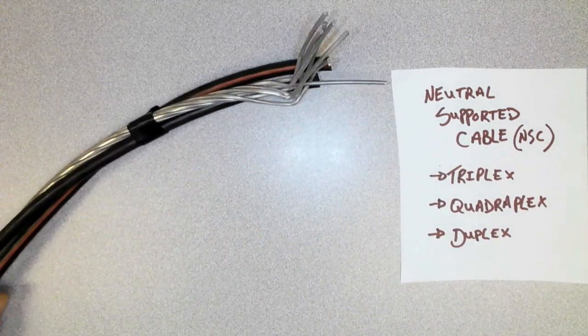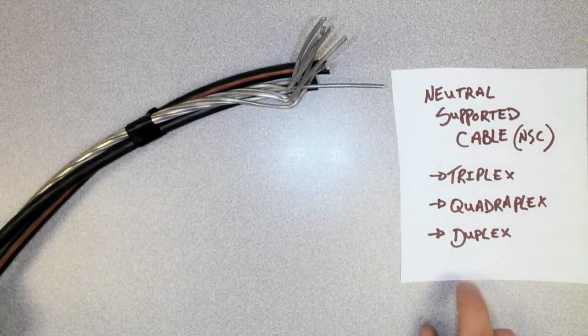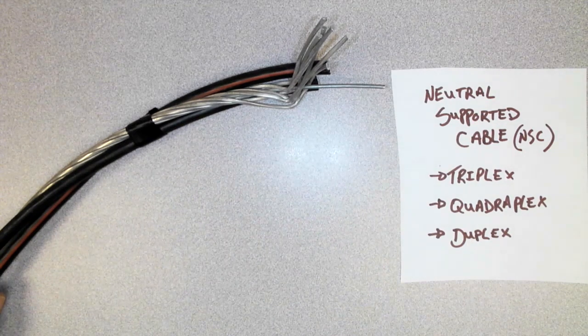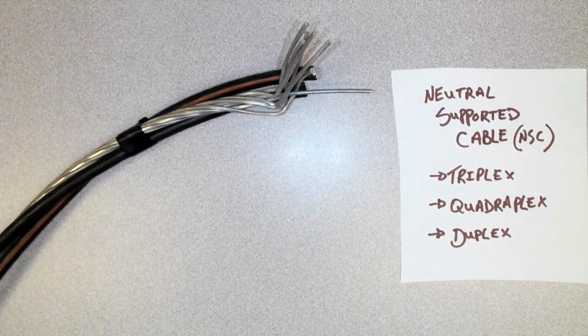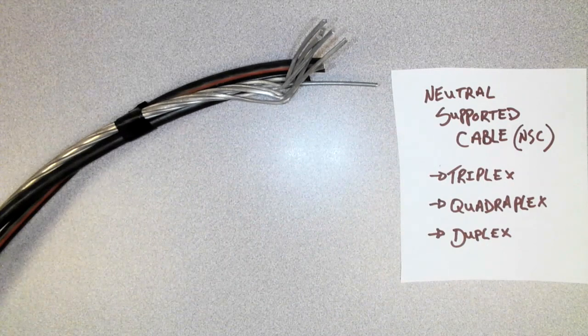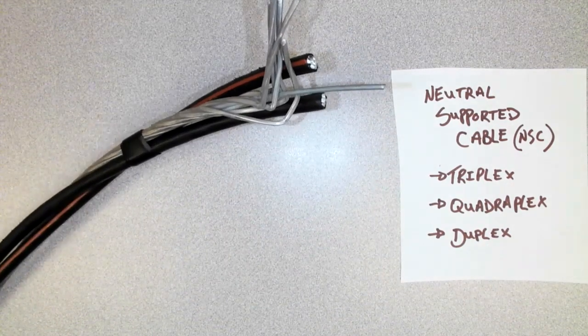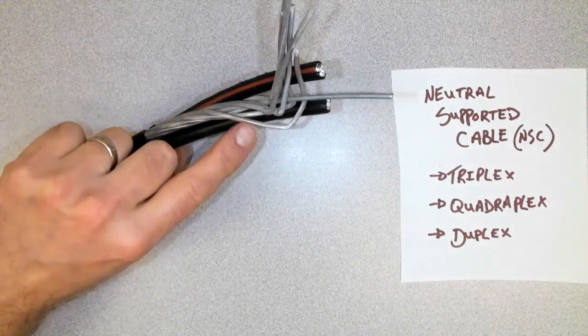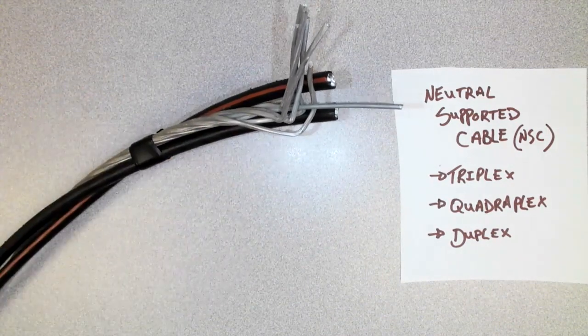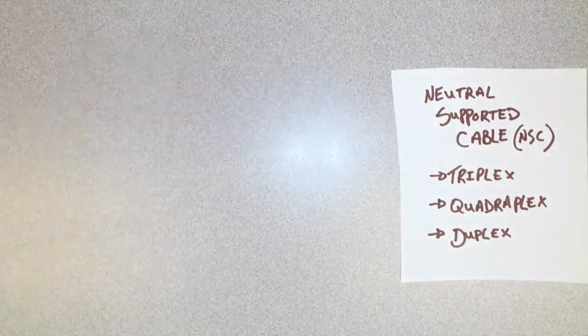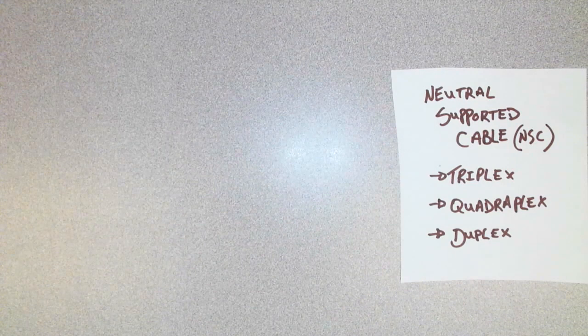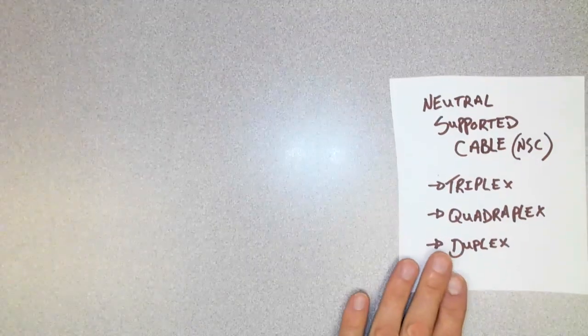Now, triplex, quadruplex, those are the two most common that we see, but it is possible to see duplex as well. And what they're referring to with the names is the number of total circuit conductors. This one has 3, line 1, line 2, and the neutral. Table 36A and 36B would be used in determining the uses for that type of cable.